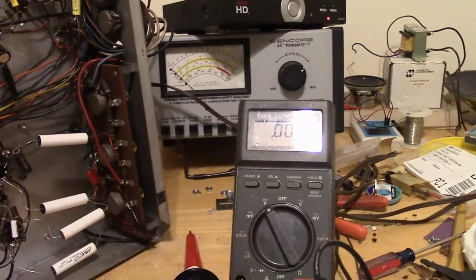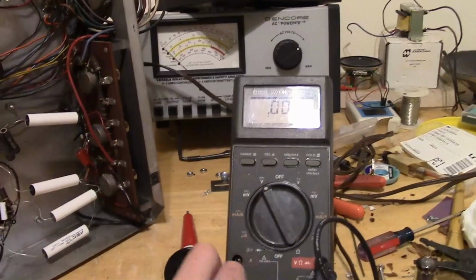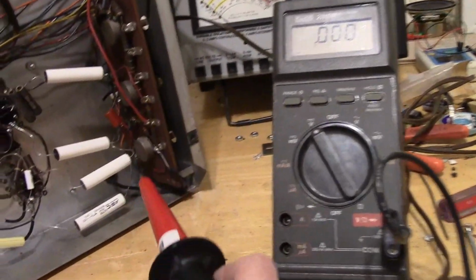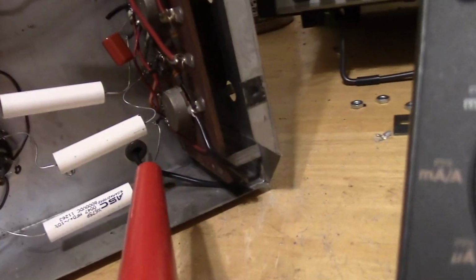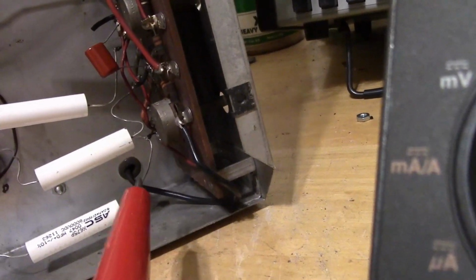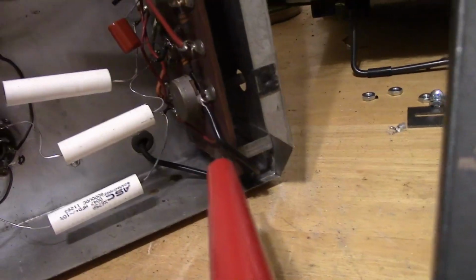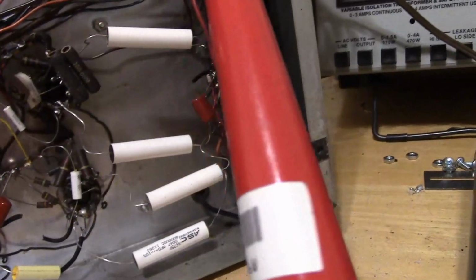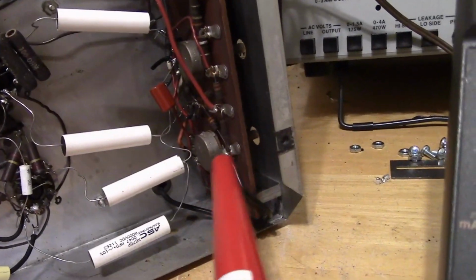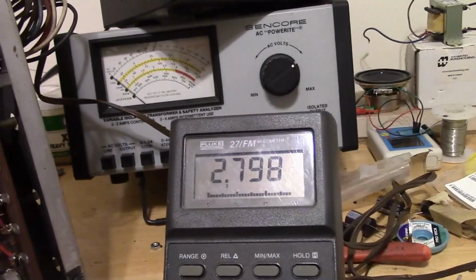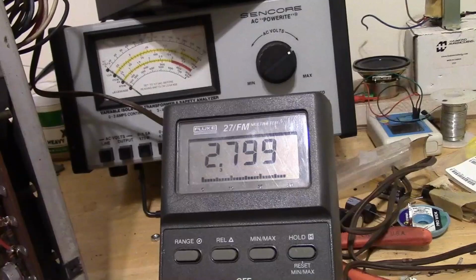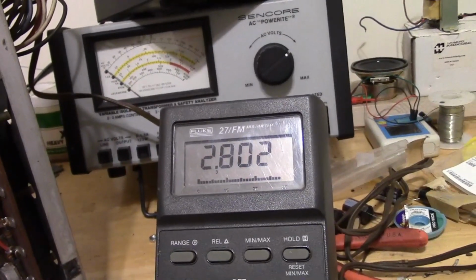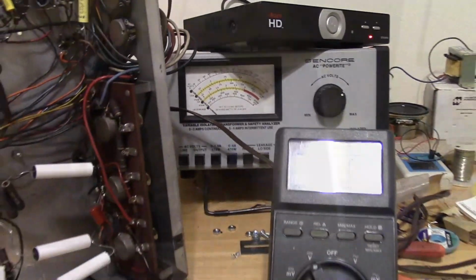Before we dig that high voltage box out, let's check what the output of it is. That's this black lead coming down through that insulating grommet - that's the high voltage output of that generator. Got my 6,000 volt probe for my Fluke, put it on there. That is way low. It should be at least 5,000 volts, so we've got about half of what it should be.